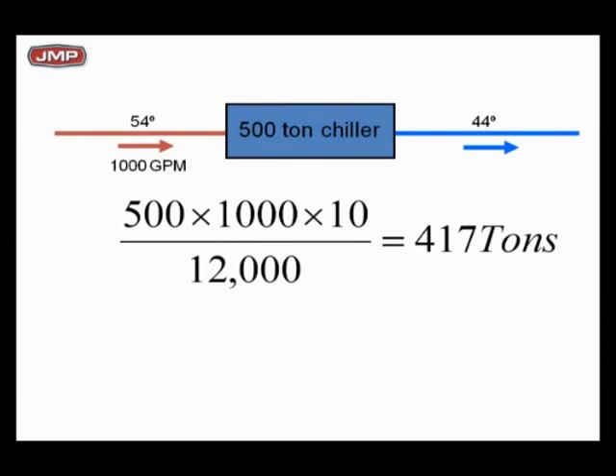Now you bought a 500 ton chiller, and make sure you get this simple statement. This is very important. I'm repeating myself. You have to get the return chill water up to design to get max delta, to get max tonnage. In other words, if you're producing 44 degree water on this 500 ton chiller, and you never give me water back any hotter than 54 at 1,000 GPM, you're never going to get more than 417 tons out of the chiller. It's impossible. You cannot get any more. You're hung. So what are you going to do? Chiller is only 83% loaded now. You bought a 500 ton chiller, and you can't get 500 tons out of it.